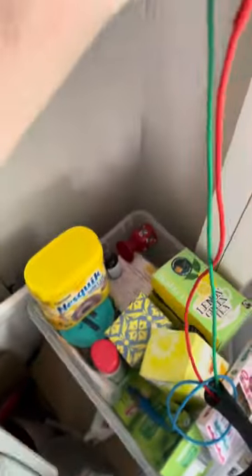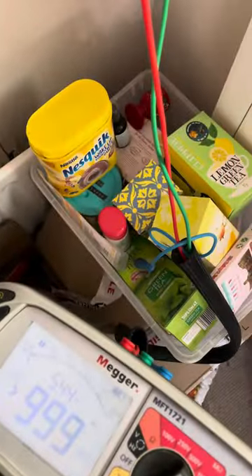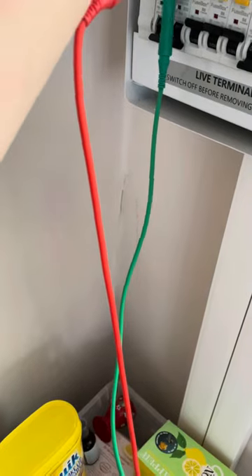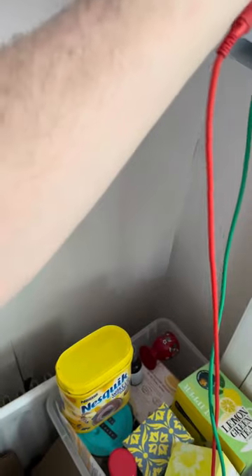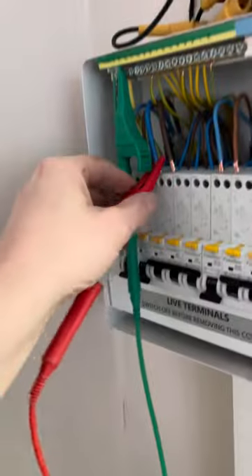Now let's go between line and neutral at 500V - lock it on. So that was line to earth CPC. There's neutral to CPC for the boiler, there's line to CPC on the hob, neutral to CPC on the hob - that's cool.